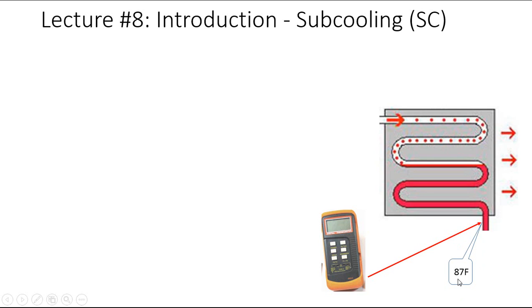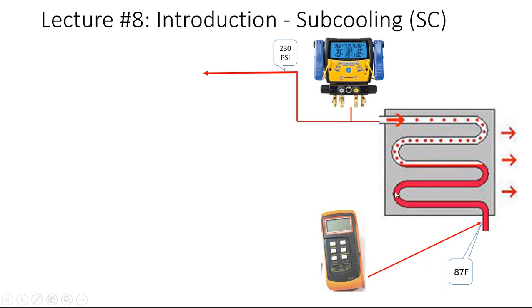So for our illustration here, we're figuring 87 degrees. So we're reading 87 degrees physical line temperature. So really what that means is the liquid refrigerant that's inside that pipe is 87 degrees. All right, so that's going to be a valuable piece of information to have. So the next thing we're going to do is we're going to take a pressure reading. So like we did before over on the superheat side, or the evaporator side of the system, we're going to take a pressure reading. And again, as we touched on before, this is a real fancy manifold or refrigeration gauge set. And we're just going to assume for right now that we're not using it to calculate our subcooling. We're going to do it the old-fashioned way. So just for our example here, we're reading 230 psi on this side of the system, because this is the higher pressure side of the system, because it's on the compressor side. So that's totally normal.